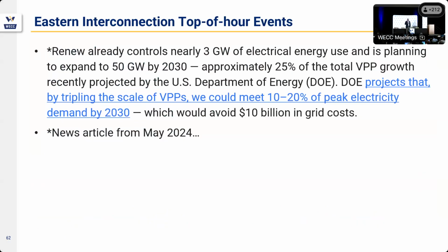So DOE projects that the tripling scale of virtual power plants could meet 10 to 20% of peak electricity demand by 2030. We have an emerging risk. The emerging risk is we built our whole world on non-predictable resource losses. And if we don't start working with these third-party vendors, it's predictable. And that means the variability goes away. And statistically, instead of 2 resource losses for our resource loss protection criteria, we probably got a plan for 3. And that's going to be a lot of money because everybody's got to carry frequency responsive reserves.